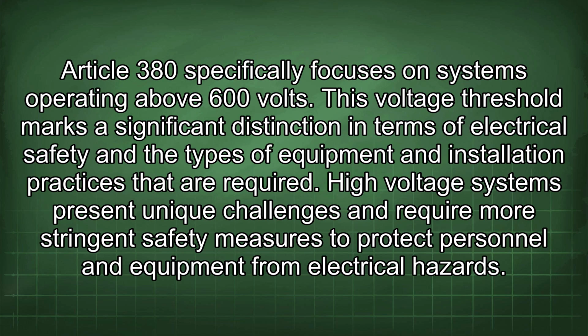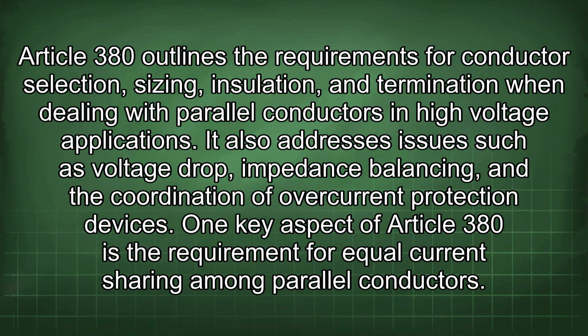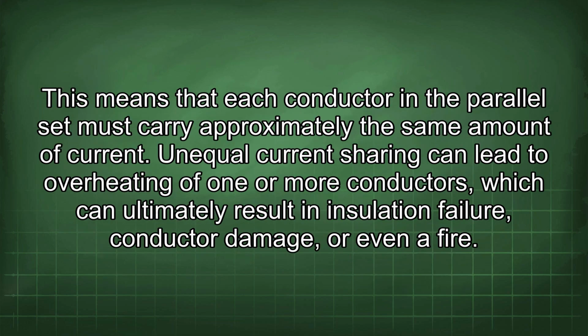Article 380 outlines the requirements for conductor selection, sizing, insulation, and termination when dealing with parallel conductors in high-voltage applications. It also addresses issues such as voltage drop, impedance balancing, and the coordination of overcurrent protection devices. One key aspect of Article 380 is the requirement for equal current sharing among parallel conductors. This means that each conductor in the parallel set must carry approximately the same amount of current. Unequal current sharing can lead to overheating of one or more conductors, which can ultimately result in insulation failure, conductor damage, or even a fire.